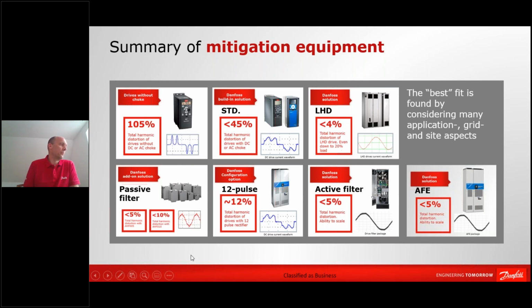Then we have the passive filters down here in the lower left corner, and you can see Danfoss offers two different versions, 5% distortion and 10% distortion, giving you THDI of 5 and 10% respectively. So again, depending on how far you want to reduce the harmonics, that could be a good solution for one or several drives in an installation. 12 pulse is also an offer that we have.